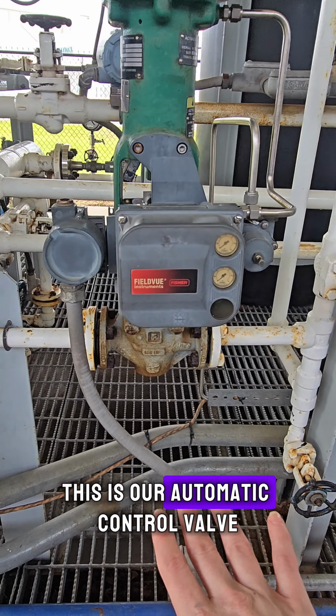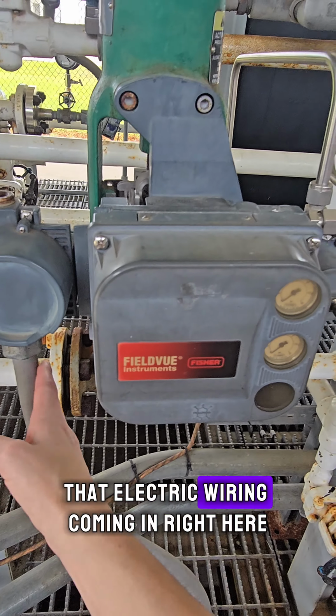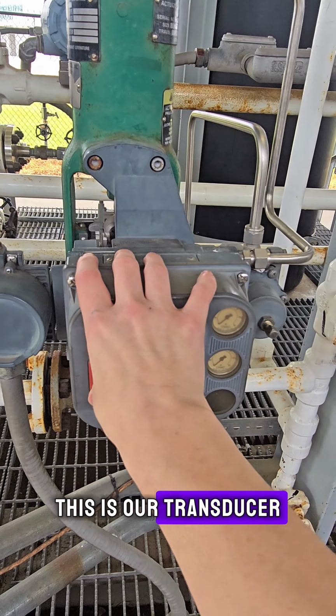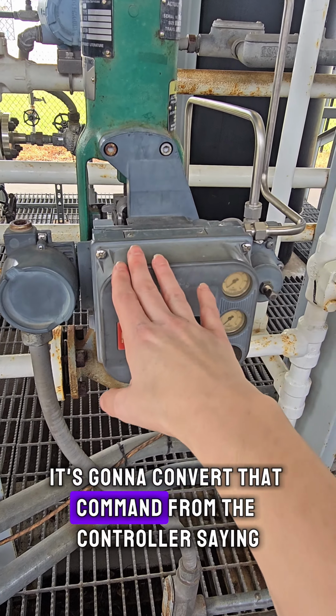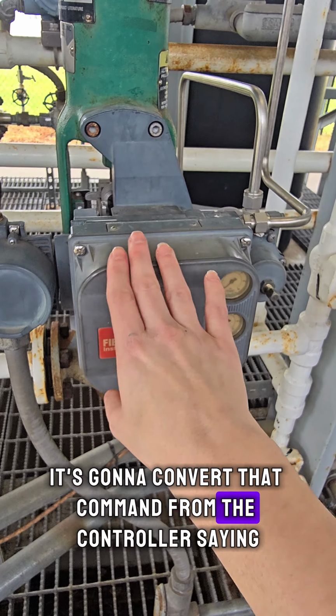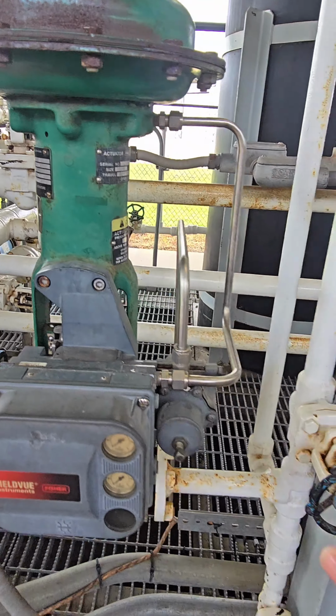So this is our automatic control valve, with that electric wiring coming in right here. This is our transducer, and it's going to convert that command from the controller saying this valve needs to be 20% open. It's going to say, okay, I need to add or take away this much air. And then this is our air tubing actually going into our diaphragm plate.